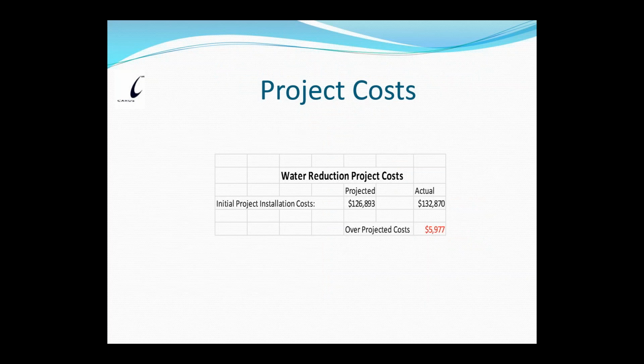Project cost: initial project installation costs, I had projected them to be $126,000. Actual was $132,000, so I was over by $5,977. One of the interesting things is when I was researching this and had to come up with the appropriately sized pump and piping, I forgot to take one thing into account when I sized the pump, and that was our incoming water pressure, which is roughly 65 psi. I sized the pump so I could pump 275 gallons a minute, but not necessarily at that pressure. Booster pumps need that inlet pressure going into their pump suctions to be able to raise that pressure once again to function properly through the water softeners.